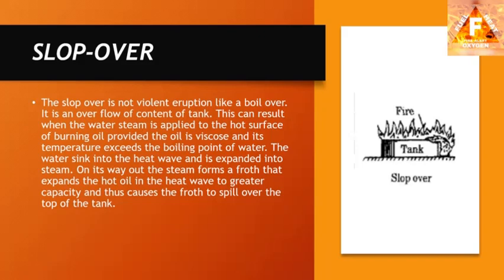When some burning liquid such as heavy fuel oils and crude oil in a tank or container become extremely hot, any water that is being applied will begin to boil. The resulting rapid expansion as the water converts to steam may cause burning fuel to overflow its containment and the fire to spread, and this event is known as slop over.